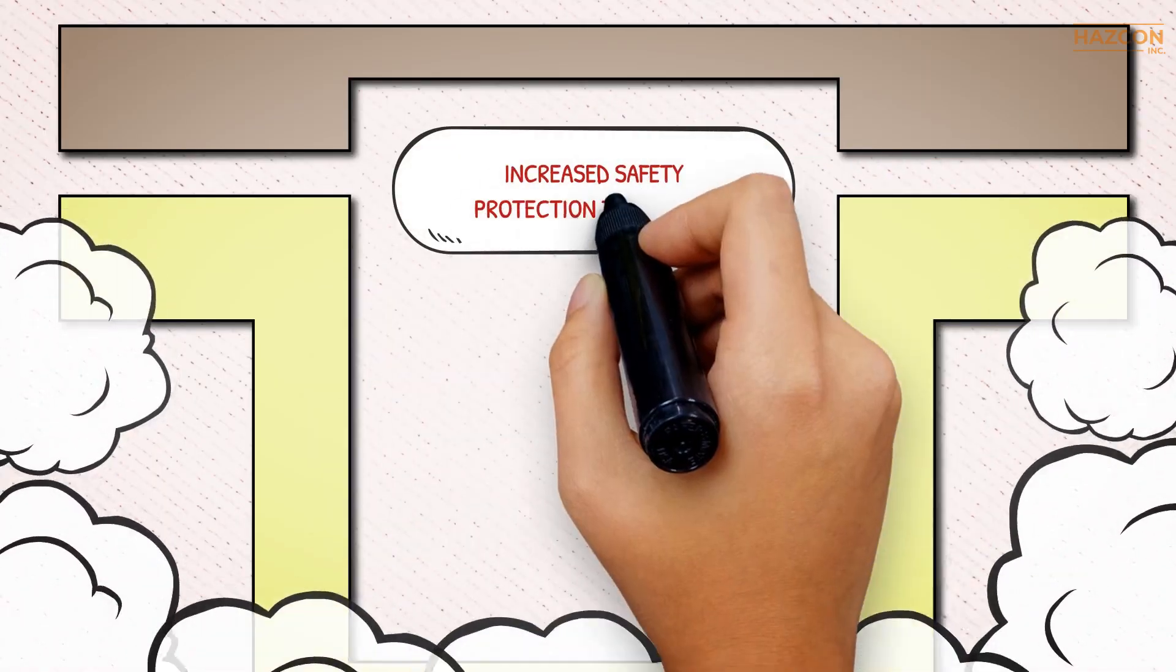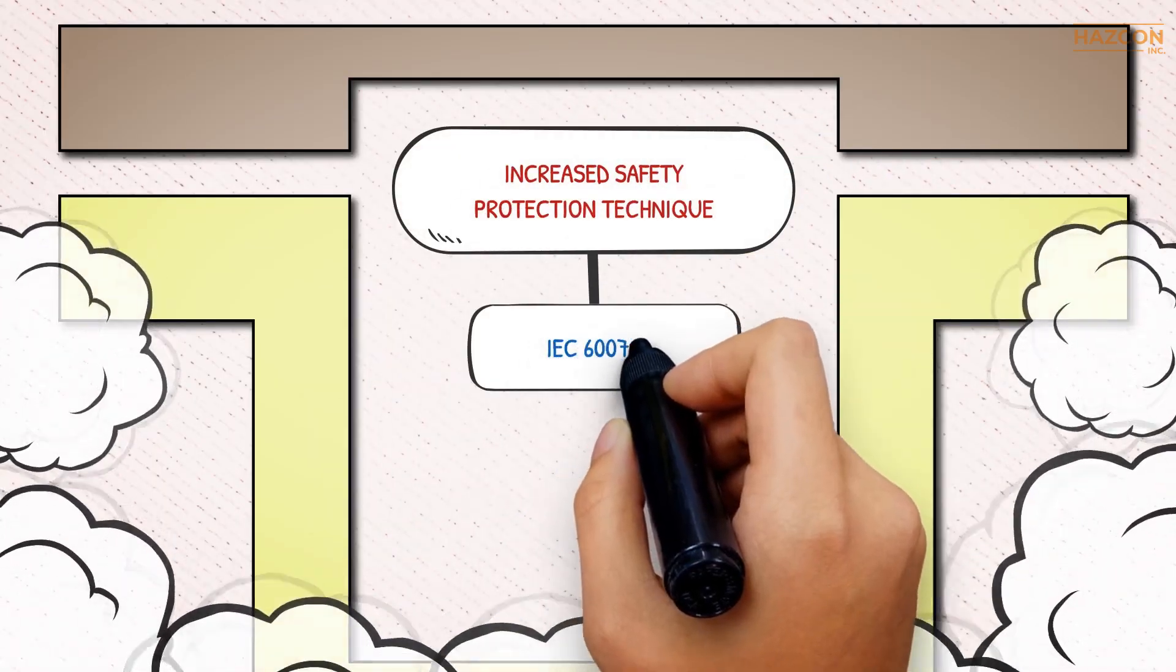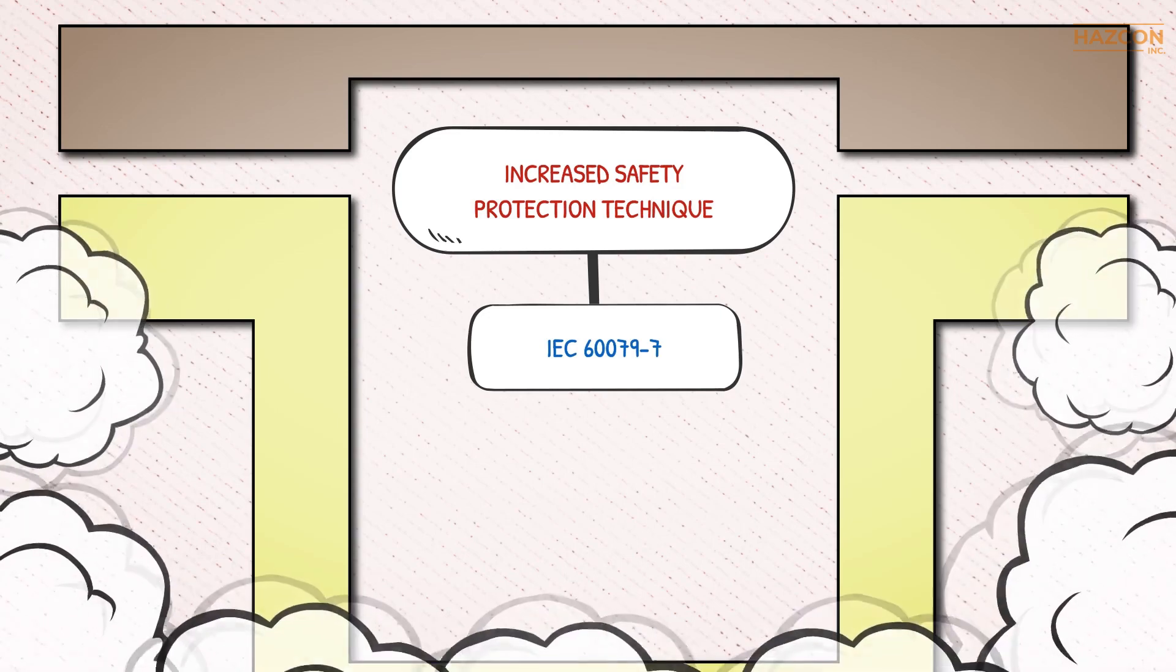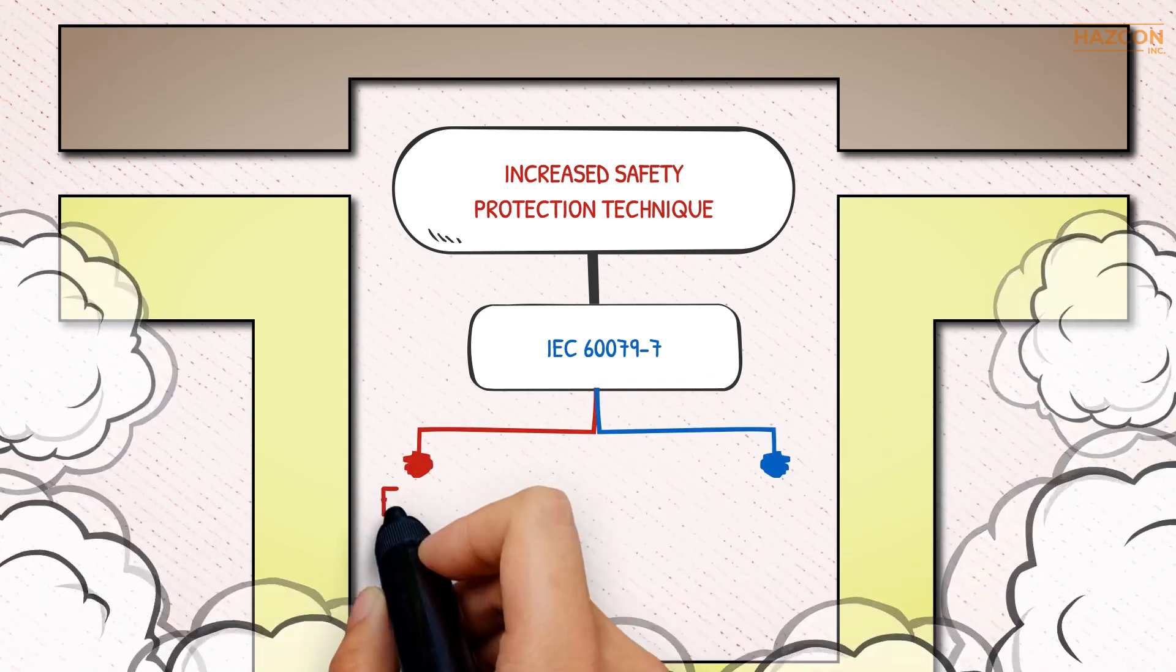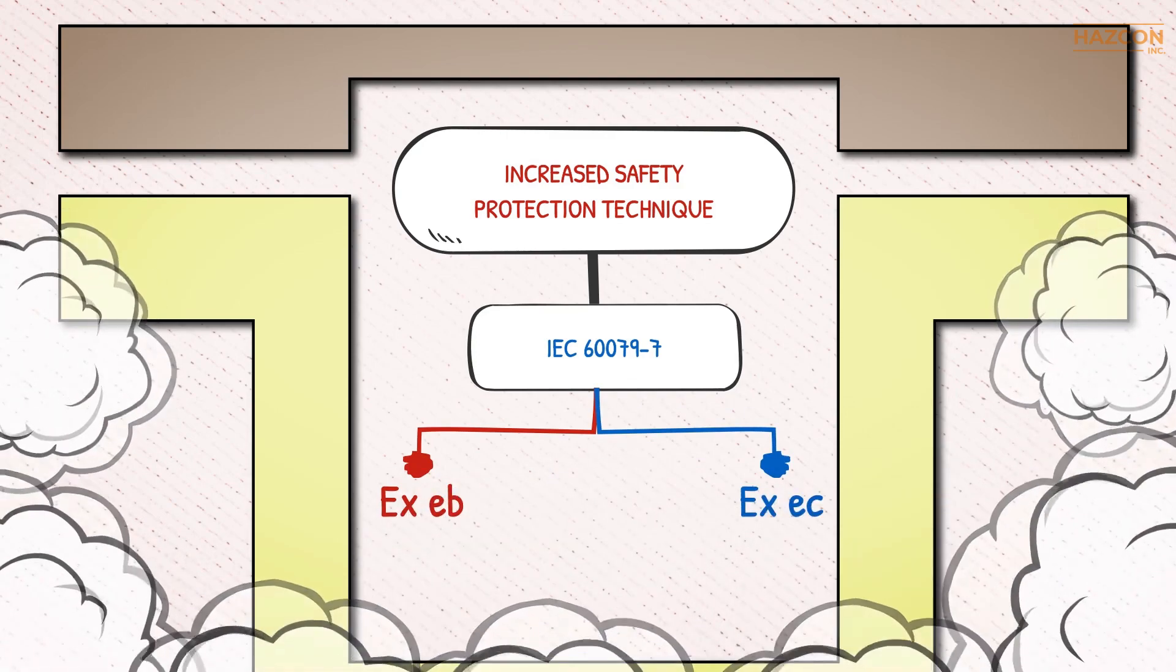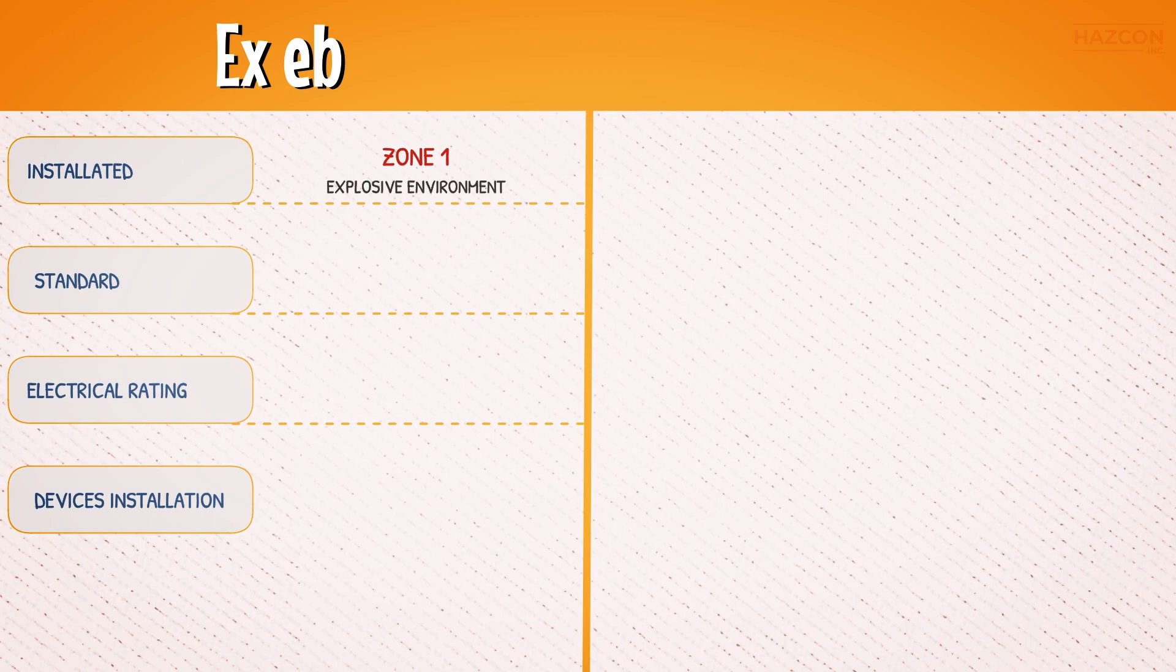To use the increased safety protection technique, equipment must comply with the IEC 60079-7 standard. There are two Ex markings and protection levels in the standard: Ex eb and Ex ec. Equipment marked Ex eb may be installed in Zone 1. As per the scope of standard IEC 60079-7, only electrical equipment with a maximum electrical rating not exceeding 11 kV may use this level of protection.